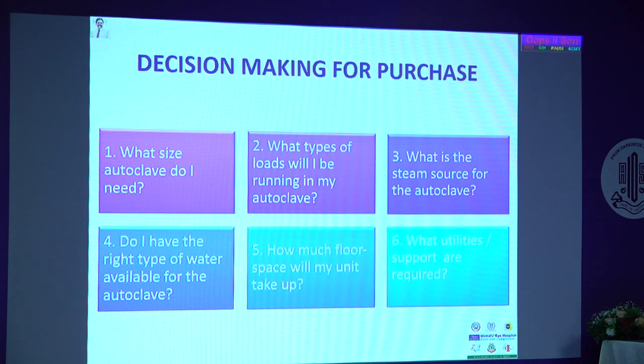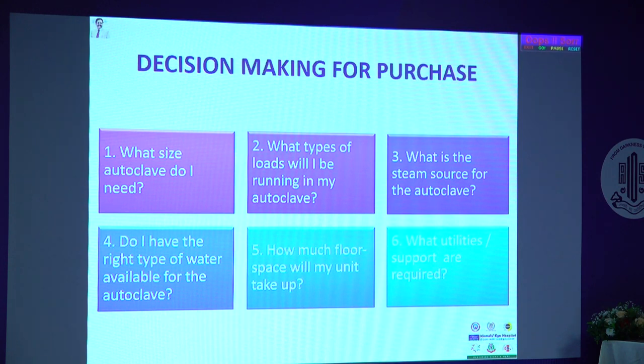For type of load: if you are going to do posterior segment surgeries and reuse your vitrectomy or phaco tubings, you need to segregate your consumables accordingly. Steam source: it is ideal to separate the steam source and use good purified water — whether RO water, distilled water, or softened water, anything is good. Use the same source consistently and check the inner linings of tubings every three months for mineralization. Floor space: always leave at least two feet of space around your autoclave — very important for maintenance, as staff often get burned in close spaces.